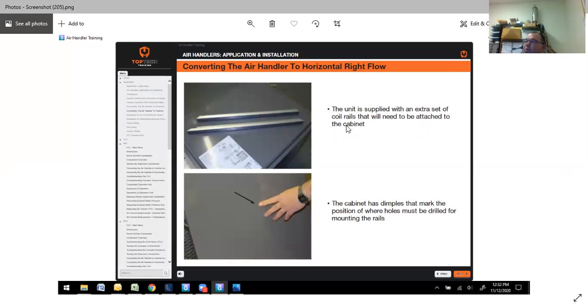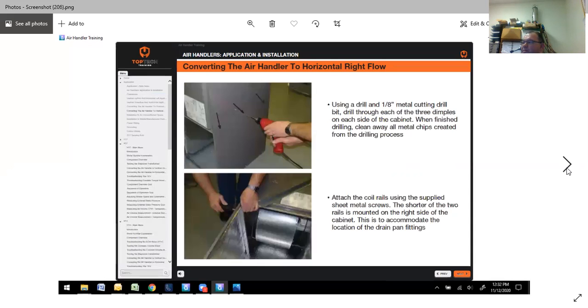The unit is supplied with an extra set of coil rails that will need to be attached to the cabinet. They are smart enough here. They actually give you some dimple holes here on the side where to mount these rails. Use a drill. It tells you an 1/8-inch metal cutting drill bit. Drill through each of the dimples. When finished drilling, sweep away any metal chips. Attach the coil rails using the specified sheet metal screws. The shorter of the 2 rails is mounted on the right side of the cabinet. This is to accommodate the location of the drain pan fittings.